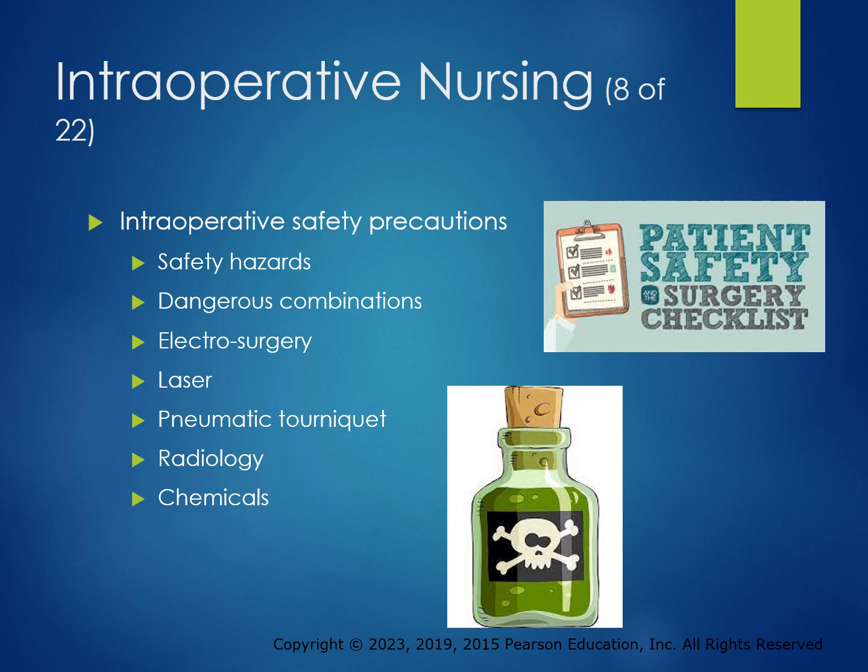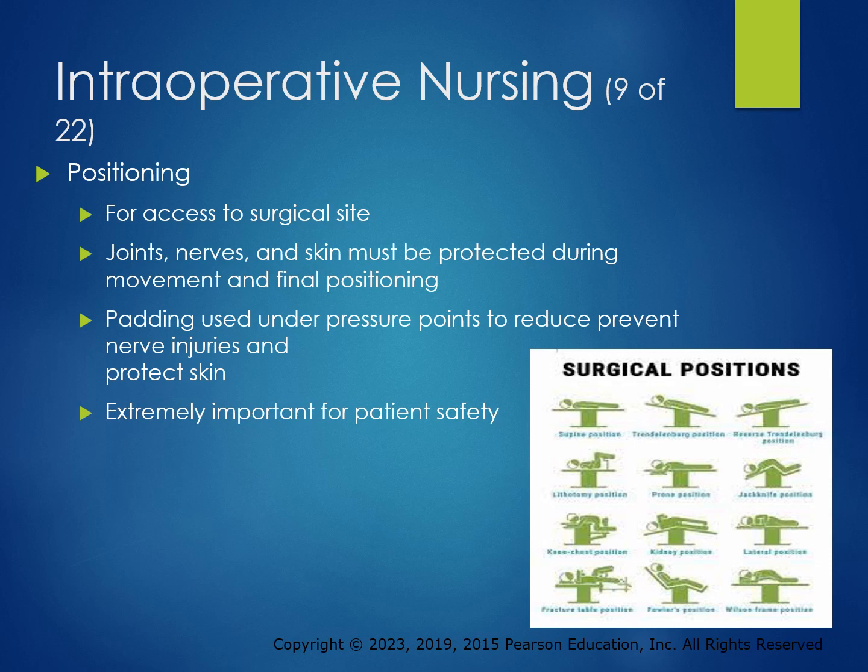Fire in the operating room can have devastating health consequences for the patient and procedure team. Before the operation begins, make sure to place the grounding pad and all electrosurgical equipment correctly to prevent injury from burns or fire. If using an alcohol-based skin antiseptic, ensure the skin is completely dry before putting on the surgical drape. And with this grounding, you've got to make sure that everything is grounded correctly, or you can cause an electrical fire.